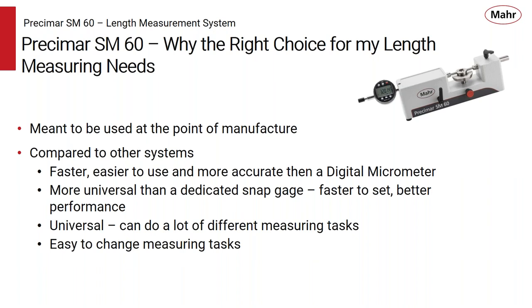It's universal. It can do a lot of different measuring tasks, whether it's IDs, lengths, measuring groove diameters and so forth. There's a lot of measuring applications the SM60 is good for. And it's, like I said, very easy to change from one measuring task to another. You use the adjustment to set the reference contact, get your part to the right height, bring your measuring anvil in contact with the part, set 0, and you're ready to go.